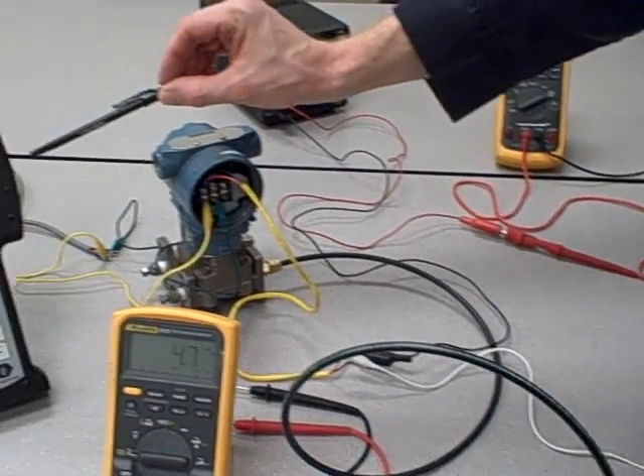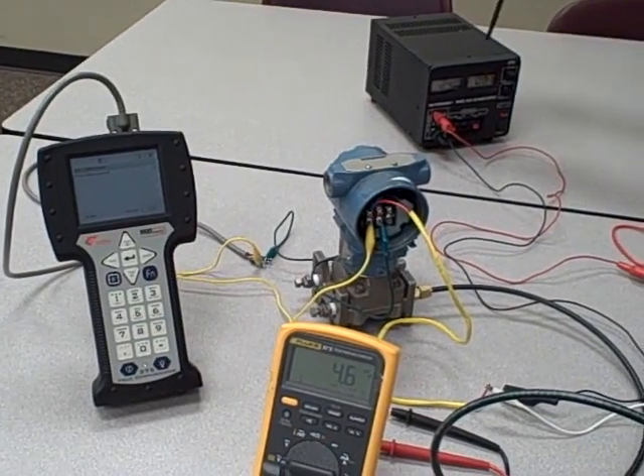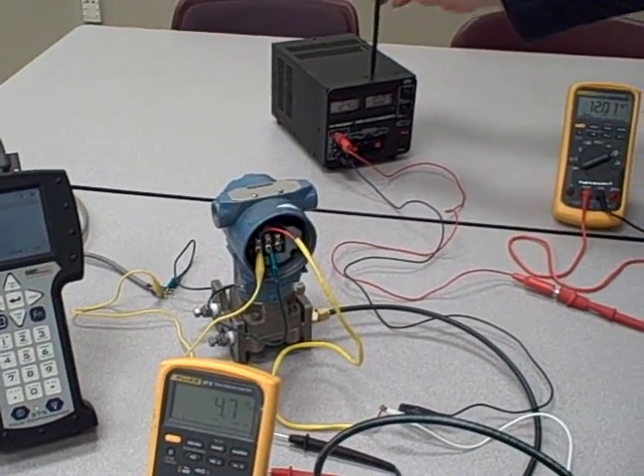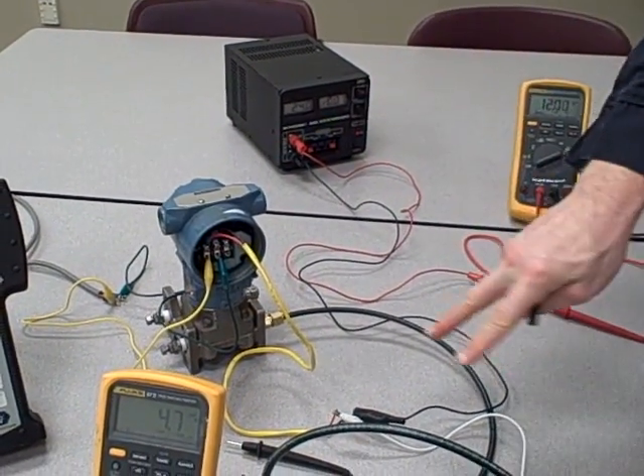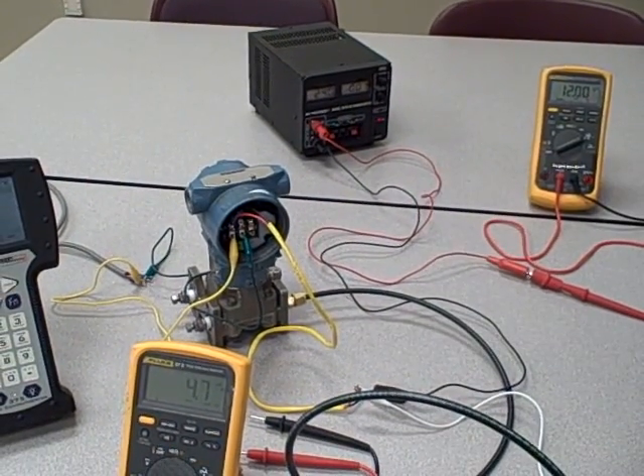Recall that the HART data signals are exactly that, AC voltages. So with the filter capacitors here on the power supply being effectively in parallel now directly with the transmitter, it squelches any attempt to communicate in digital form.